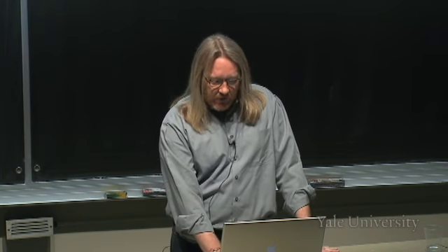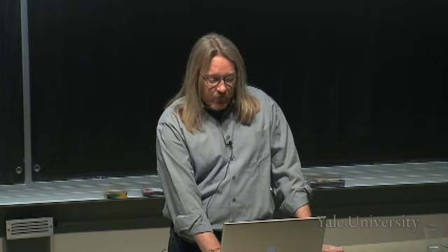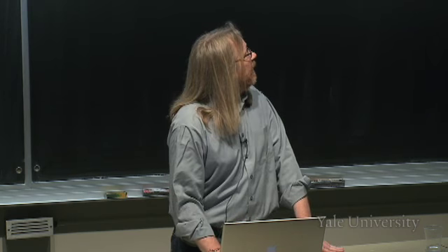So here's an early example of a mechanical valve, a totally synthetic material that could be used to replace a heart valve. Now this is a collar here, which is made of a textile that can be sewn in to the spot, to the ring of tissue where the heart valve goes. So you can see that white material there. There's a metal ring underneath it, and on both sides of this ring there's a cage, a small cage on the bottom and a larger cage on the top. Right? So the heart would be down here. The ventricle would be down below this here.